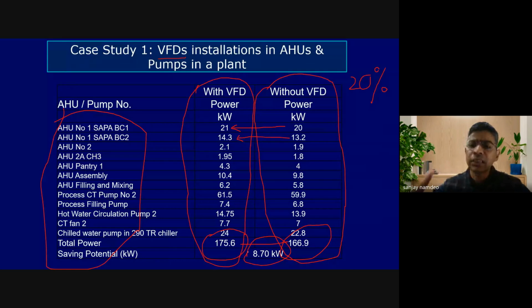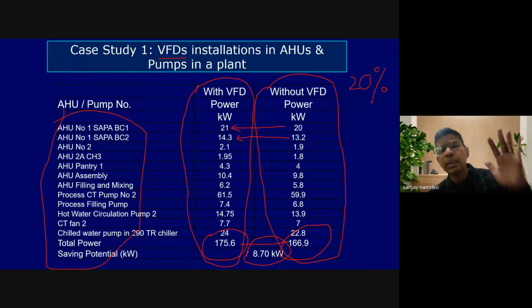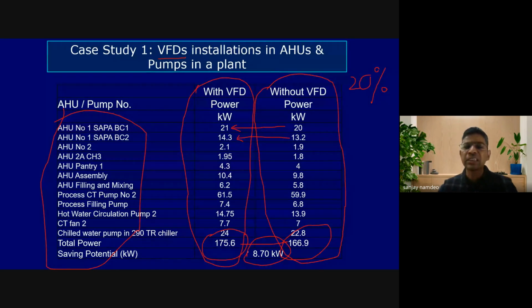There are some technical reasons. For example, the VFD is meant for variable load. So when we put in a VFD, we have to reduce its frequency, or reduce its output. If the VFD is running at full speed or full output, it will not save any power, but the VFD will have its own inefficiencies, and with that inefficiency the power consumption will slightly go up. Now you can imagine the investment made for all these VFDs. In this case, the VFD investment would be around 10 to 15 lakhs. And with 10 to 15 lakhs of investment, the power consumption has gone up by 8.7 kilowatt.